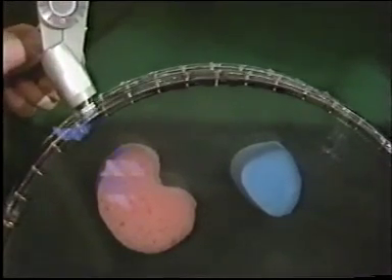Scanning the transducer around in exactly the same way as one would scan the transducer over the stomach of a pregnant woman. It's very important to maintain the transducer in contact all the time with the surface. And we've used a thin film of oil to give good contact. And by the time I get right round the other side, we should have built up quite a reasonable picture.